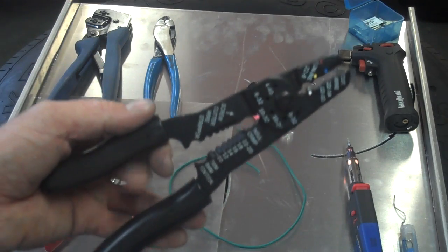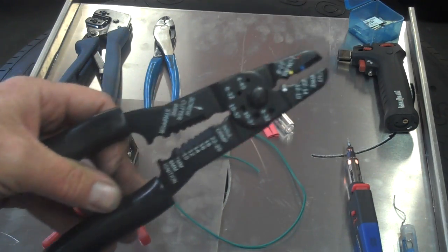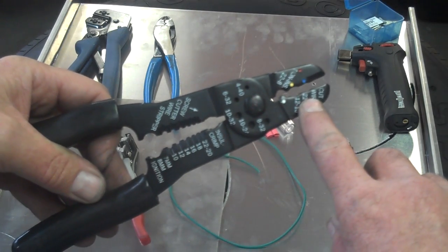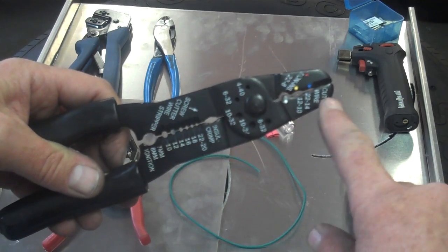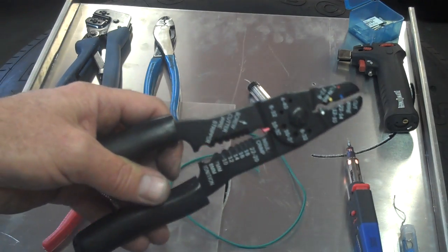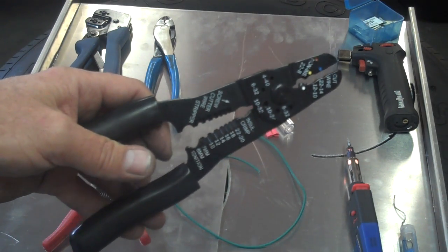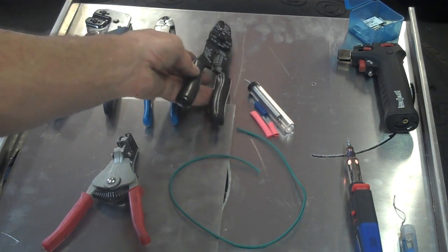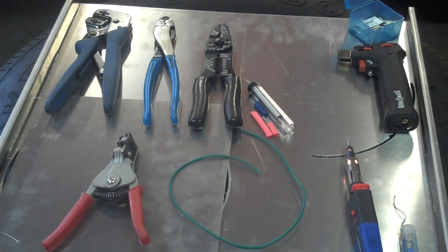This right here is probably the worst of all of them, and this is the type that's most commonly found in toolboxes. It has provisions for insulated terminals and non-insulated terminals. Problem is that none of these really give you a good crimp, so the connection ends up being a little bit loose. That looseness increases the resistance in the circuit that you're working with.